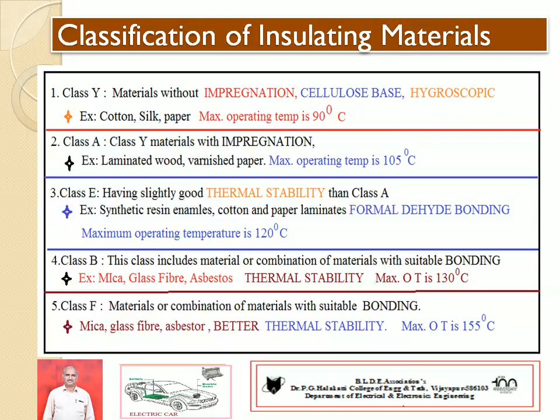Next, class E. Class E has slightly better thermal stability than class A. These are usually referred to as synthetic resin enamels, cotton and paper laminates, formaldehyde bonding. Maximum operating temperature is 120 degrees centigrade. Next, class B. This class includes a combination of materials with suitable bonding. Examples are mica, glass, fiber. Similarly follows class F, slightly improving, again using bonding. It is 155 degrees centigrade.